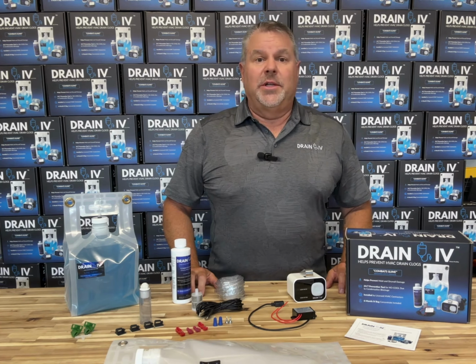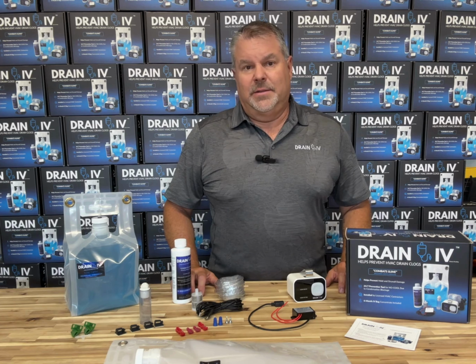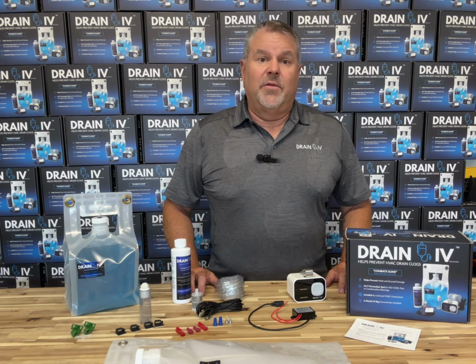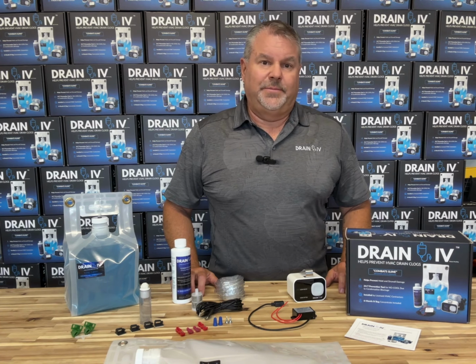Installation of this product by anyone other than a licensed HVAC or electrical contractor voids the warranty. So please make sure your installation conforms to local building codes. The air handler's drip tray and drain line must be thoroughly cleaned prior to installation. And please, don't forget to turn off the air handler's power before removing the control box cover.